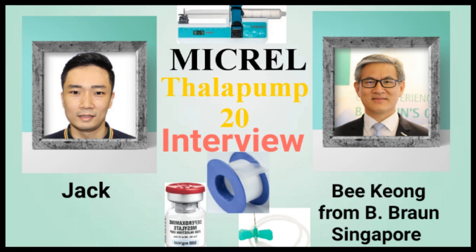Can you share with us some of the key benefits of using this pump? So first of all, since this pump has been in use for Thalassemia patients for many years, it is designed to be simple to use. It is also robust — it can withstand everyday knocks and drops. It is lightweight at 220 grams with six AAA batteries, and on a single battery set you can run approximately up to two months with a 50ml per day infusion. It can accept many syringe sizes: 10ml, 20ml, 30ml, 50ml, and 60ml, with an accuracy of plus or minus 2%. These are some of the key benefits of the Thalapump 20 that will make life easier for users.